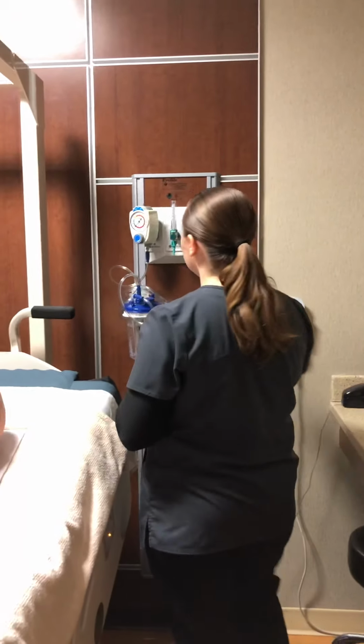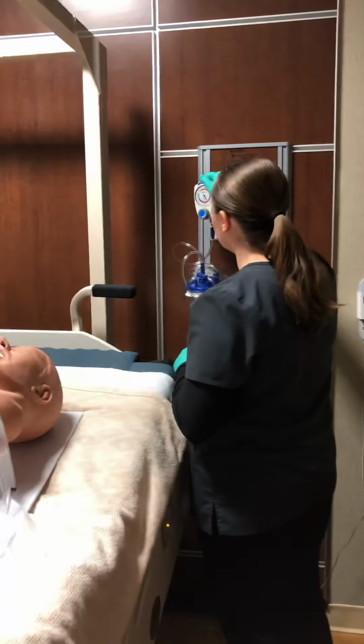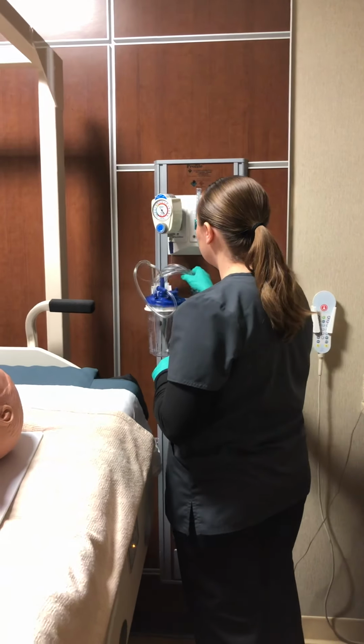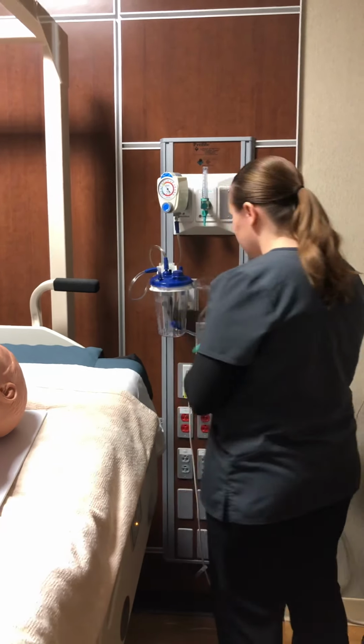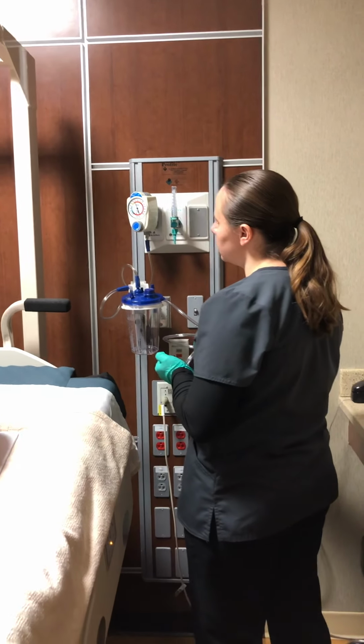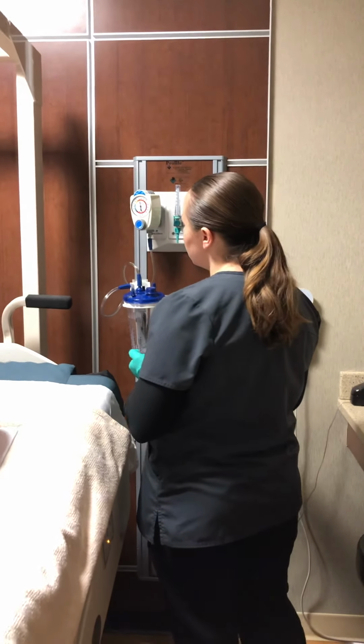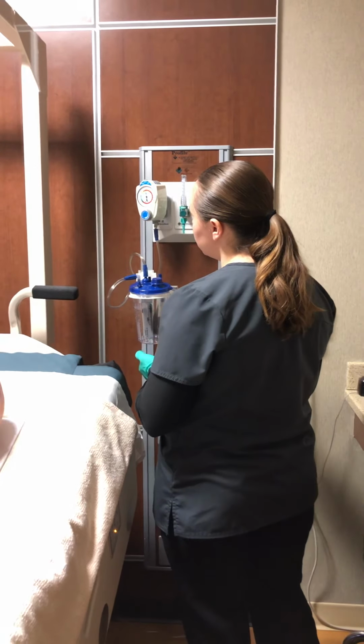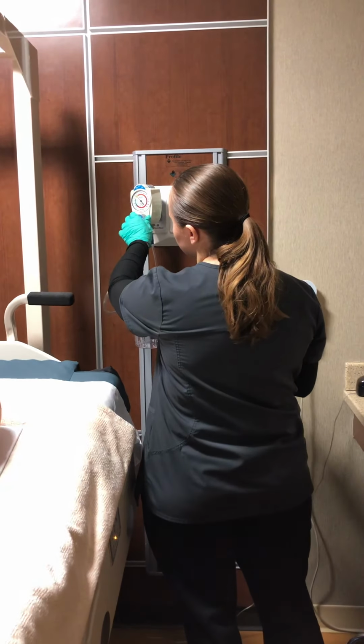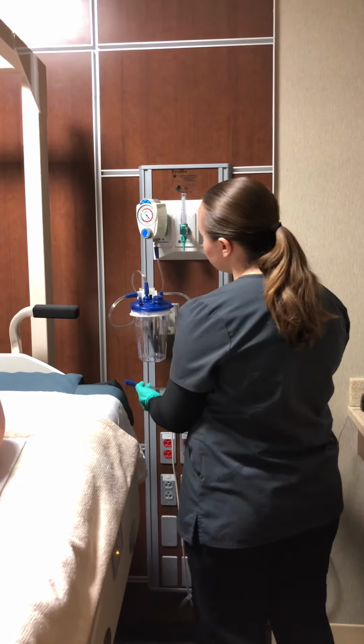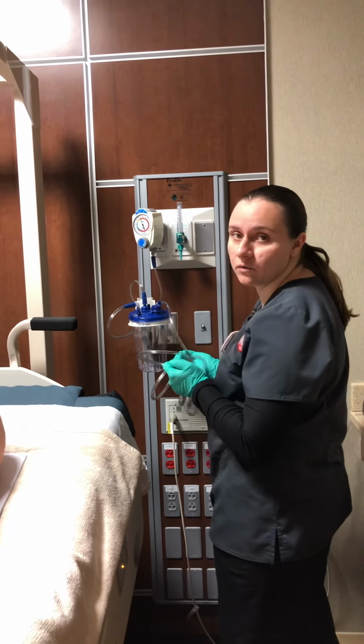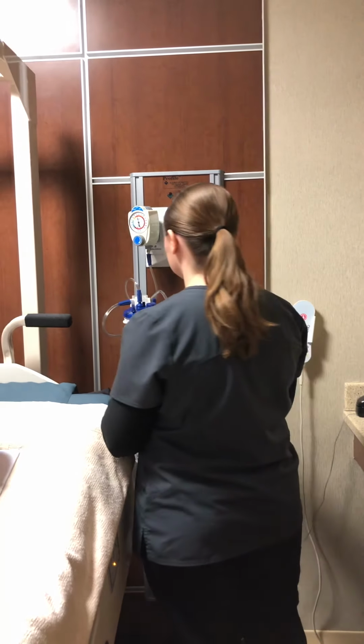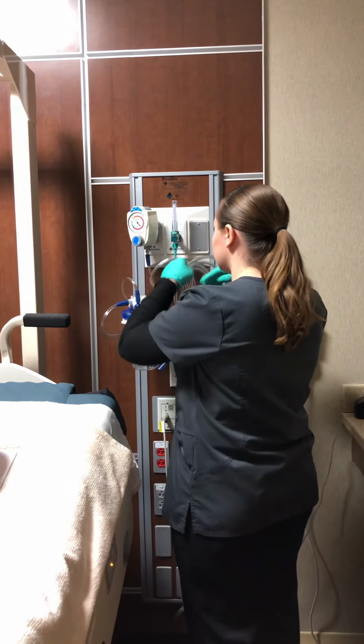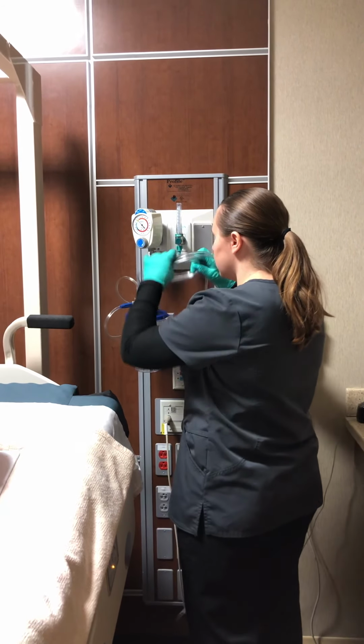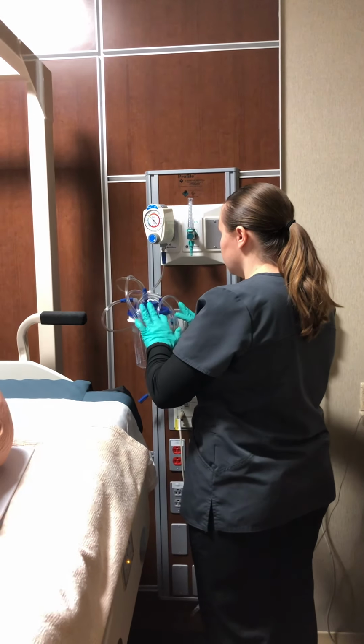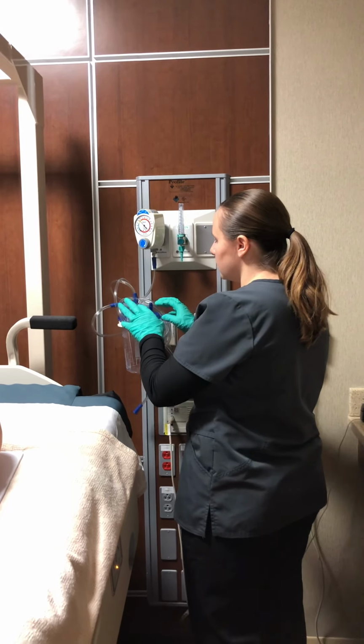So I'm going ahead and set up my regulator here, the vacuum, and I'm going to get it ready. So what I'm going to do is check the end piece to make sure it doesn't go above -150, and if it does, we can lower it down and recheck to make sure it stays in between -120 and -150. So when it's ready, then we can just set it off here to the side. Make sure nothing falls and touches the floor.